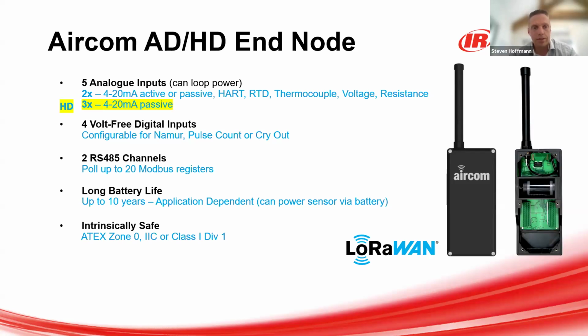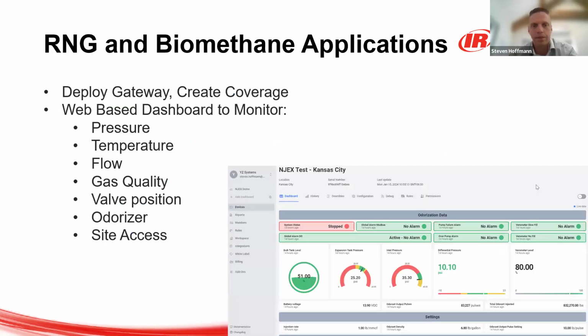4 volt-free digital inputs. Those are configurable. The first 2 can be configured as a pulse count input for, say, a flow meter that you may have monitoring gas. And then the last 2 can be configured as a cry out function. So if you set up your data to be sent back every 5 minutes with that cry out feature, if it detects a change in state on that digital, it'll wake up and send immediately. So if you have it connected to, say, an alarm input or something like that, you'll be notified immediately. 2 RS-485 channels for bringing back Modbus data. So up to 20 Modbus registers can be sent back. And that long battery life we talked about before and the intrinsically safe design that can be put right there in the hazardous area are what make this product line a real advantage. You go to the next slide, please.